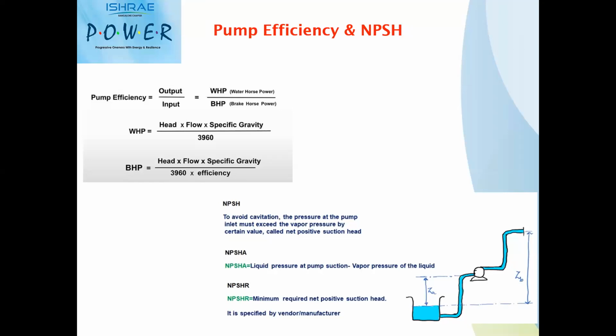And generally, when we are designing any HVAC plant, efficiency is also a very big factor which decides our total IKW per TR output of the chilled water plant. So in this case, whenever design consultants or design engineers are designing a particular pumping system, they will have minimum efficiency criteria also defined for particular pumps. So basically, whatever efficiency figures we are giving in terms of pumps is the output by input. Output is nothing but the flow and head we are getting out of the pump. So head and flow into specific gravity.